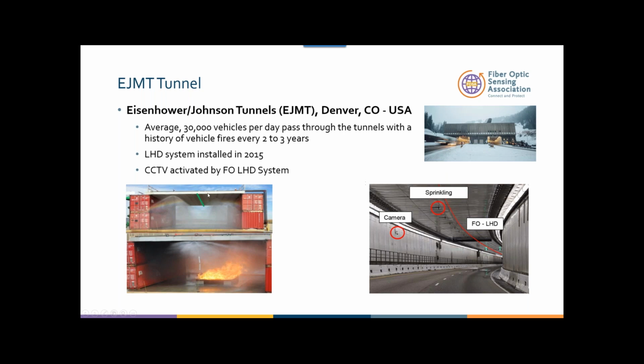before installing this fiber optic linear detection system in this tunnel, the client, which is CDOT, had to make sure that we are meeting the requirement from a sprinkler point of view, from a camera point of view, from a fiber optic linear detection system point of view: the ability to detect the fire and suppress that fire. The suppression is the most important key here. We are not trying to put down the fire, but we are trying to suppress it so that somebody can make a decision, or the fire crew on site can go in the tunnel and intervene and save lives.